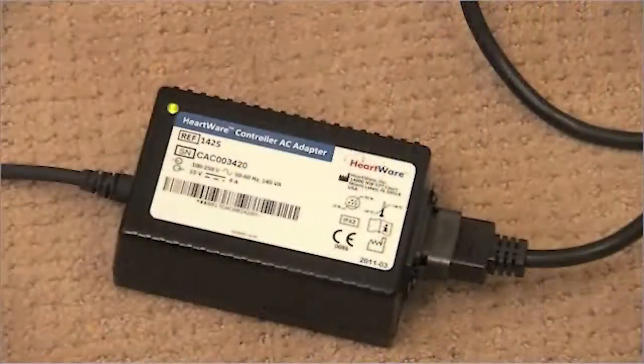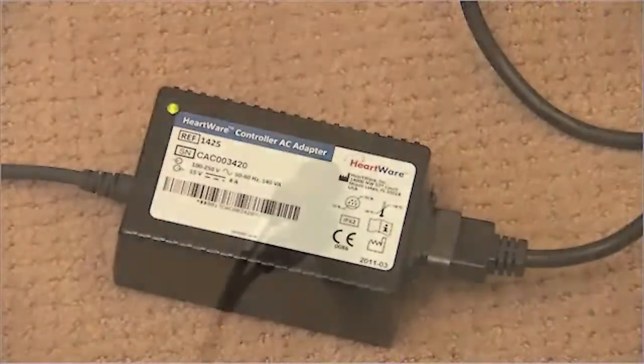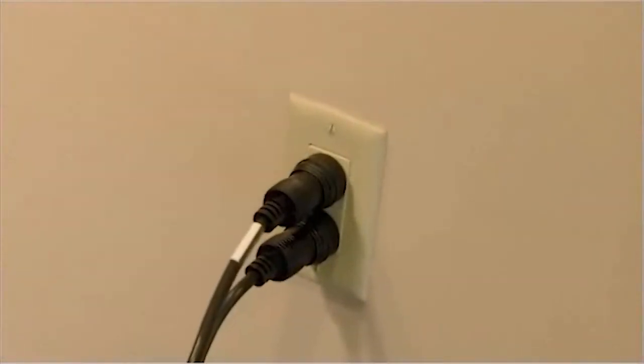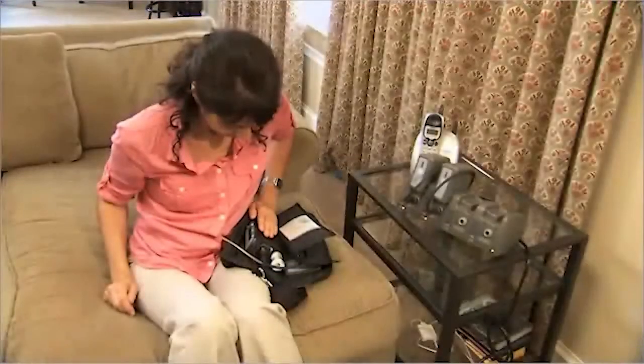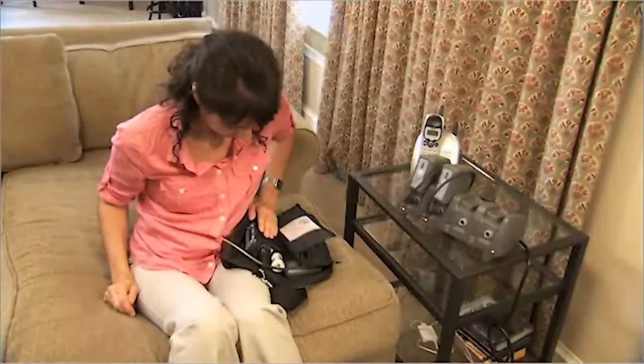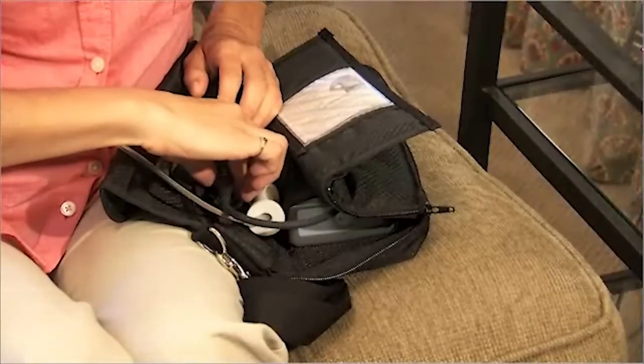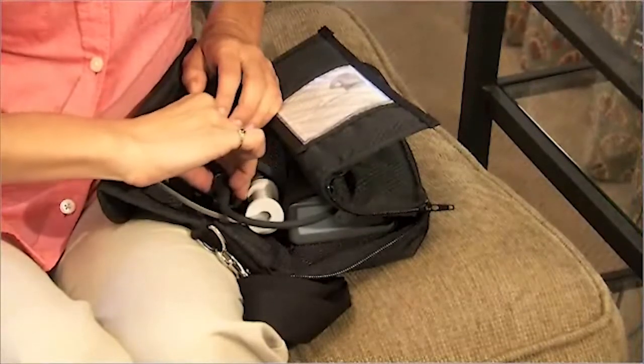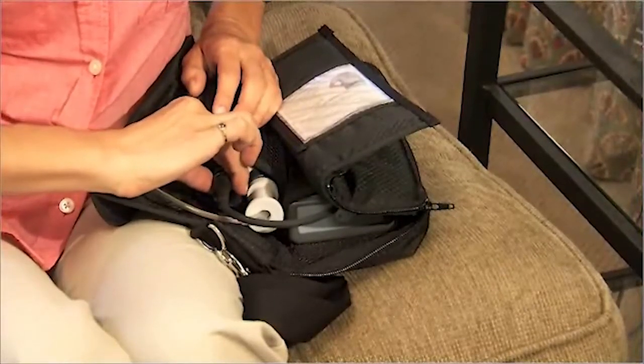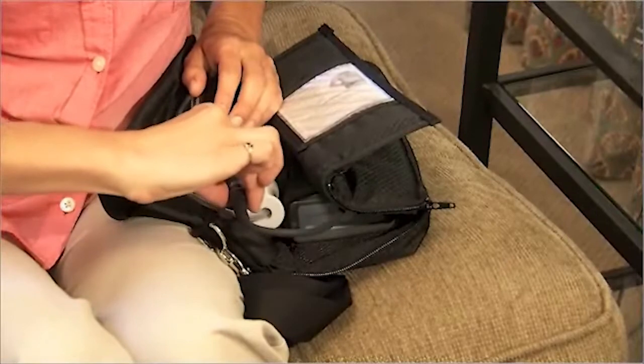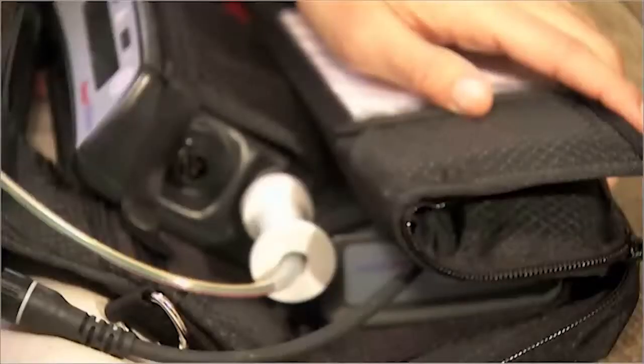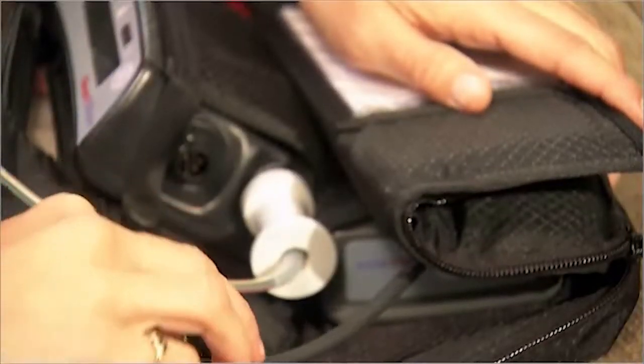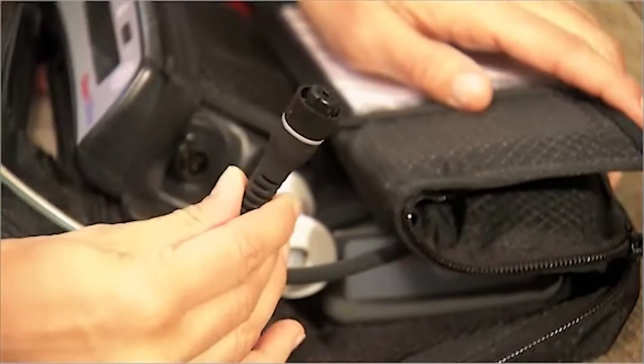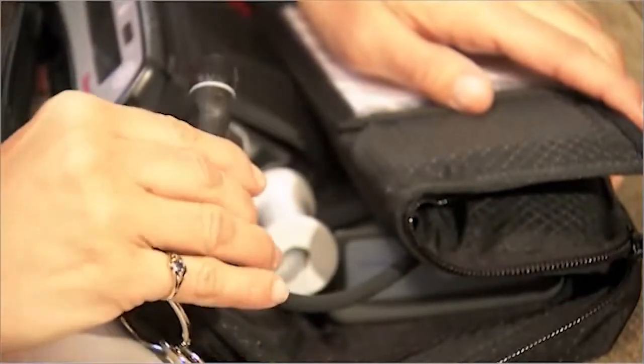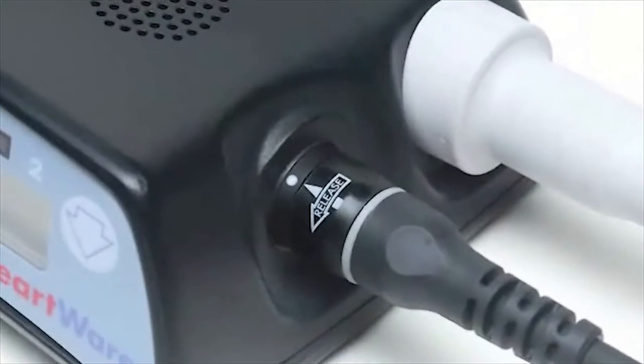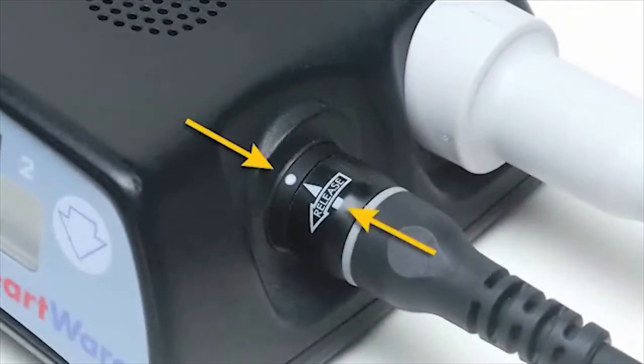If the controller is being powered by an AC adapter, you will need to change power supplies. To disconnect any power connector, as the patient demonstrates, grasp the power cable on the front end of the connector. Turn the connector counterclockwise until it stops. Pull it straight out from the controller. Connect a battery to the controller by grasping the power cable at the back of the connector, leaving the front free to rotate.